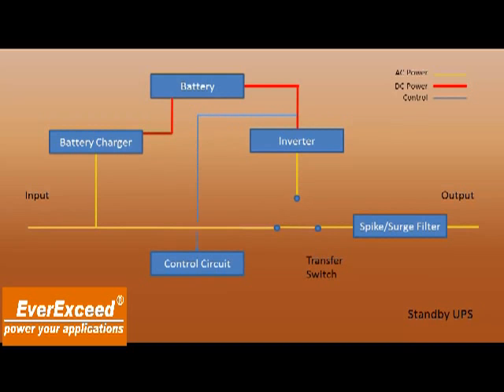This will be the circuit in place where it receives voltage information from the battery. In turn, we'll be able to turn on the battery charger when that voltage is too low. It looks at the incoming line voltage. If that voltage is out of specification, it can activate the inverter. It also has a connection to the transfer switch so it can transfer over to battery power. There will be an alarm circuit designed to tell you that something is out of whack with the system.